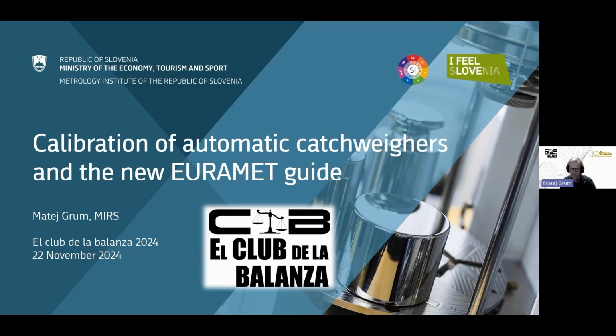I will present a very new guide among other EURAMET guides. It's dedicated to the calibration of automatic catchweighers. Probably you could be familiar with the EURAMET guide for non-automatic weighing instruments, but it was a challenge and a need from the European industry to develop a guide to cover the field of automatic weighing instruments, especially the automatic catchweighers.